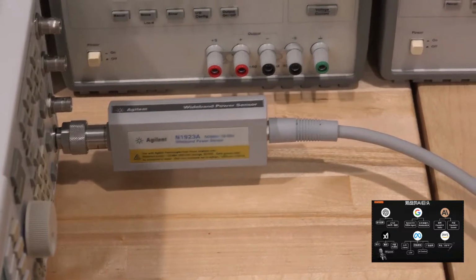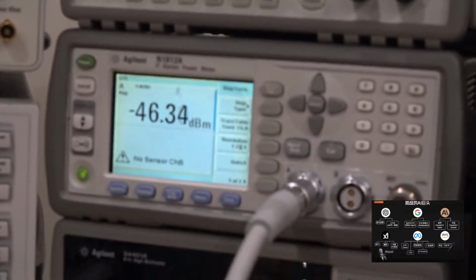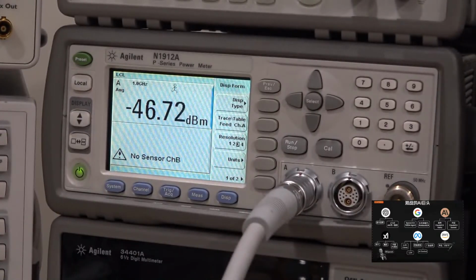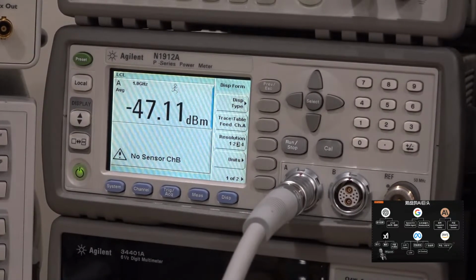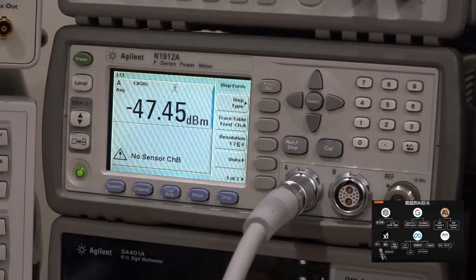The power sensor has been zeroed and calibrated and everything. So let's go over here. And what do we see? There it is. There's our power meter. You can see it's showing minus 46 dBm. It's going to go up and down by a few dB. At this range, it's within the uncertainty of the power sensor itself.